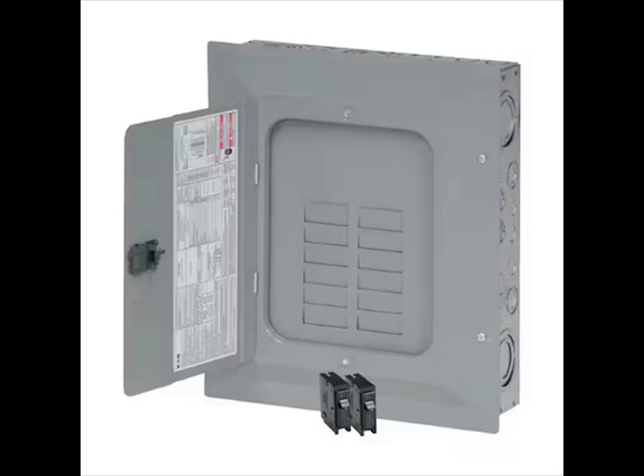Why did I need so many circuit breaker slots? Well, by code, the kitchen alone needed 7 circuit breakers. 4 appliances required dedicated breakers: the microwave, fridge, dishwasher, and stove. And my outlets required 3 breakers, and you can wire 2 outlets max per breaker.